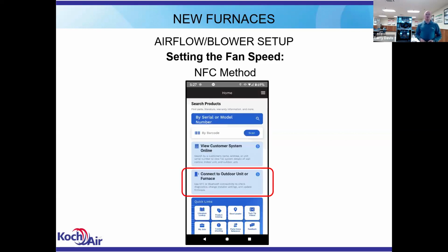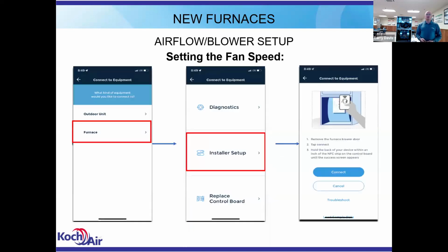So you're going to select continue as a guest, and then you're going to get this screen. You have an option to connect to an outdoor unit or furnace. So you're going to select connect to the outdoor unit or furnace, and you're going to select furnace. The newer versions are going to ask you if you want to do NFC or Bluetooth. With Bluetooth on the premium tier products, you do have to be logged in to connect to the Bluetooth. The app won't allow you to connect to a Bluetooth module as a guest. So that's the only caveat there. But you don't need to do that to do anything with the board. You're going to select the furnace, and you're going to go to the installer setup menu.